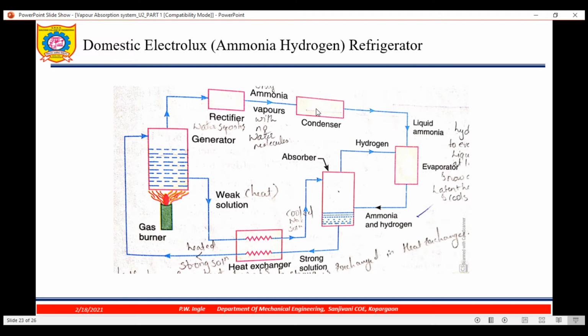Now ammonia vapor goes to the condenser, so condensation occurs. Then it goes to the evaporator, and then to the absorber. Since the ammonia vapor is separated by the heating supplied by the gas burner, we are heating the weak solution. This weak solution is supplied again to the absorber. Now this weak solution is nothing but water. There is a heat exchanger in which heat exchange takes place between the weak solution and the strong solution. The weak solution gives its heat to the strong solution, which is coming from the absorber.